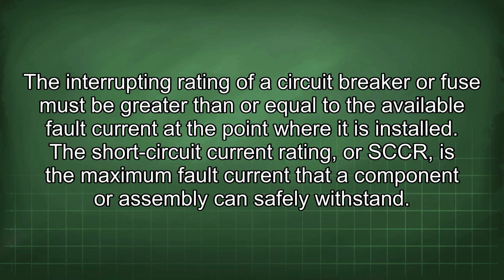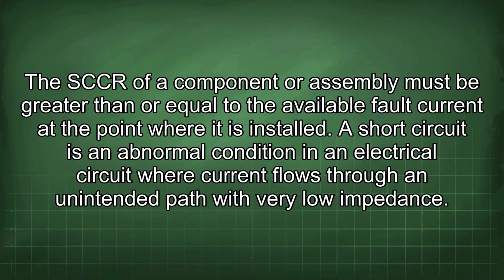The interrupting rating of a circuit breaker or fuse must be greater than or equal to the available fault current at the point where it is installed. The short circuit current rating, or SCCR, is the maximum fault current that a component or assembly can safely withstand. The SCCR of a component or assembly must be greater than or equal to the available fault current at the point where it is installed.